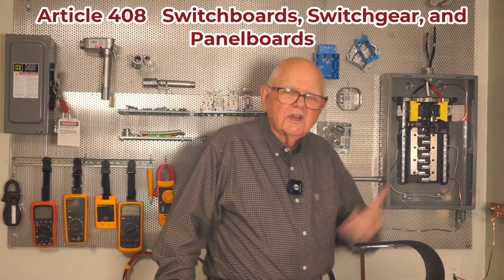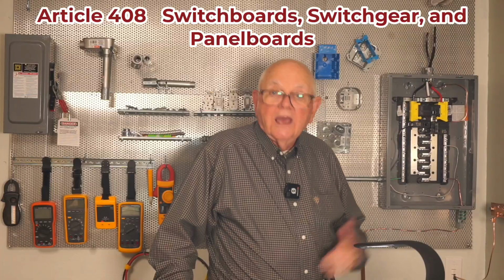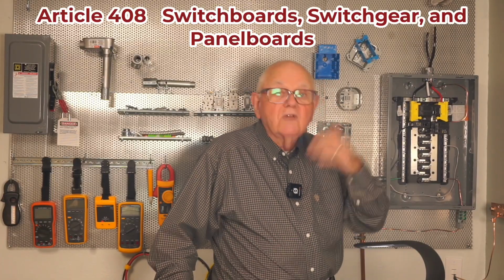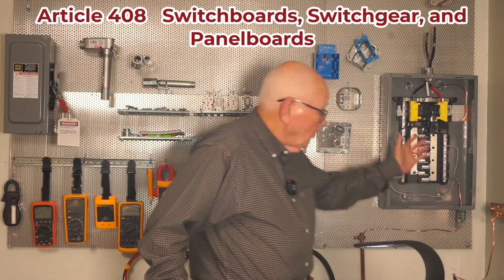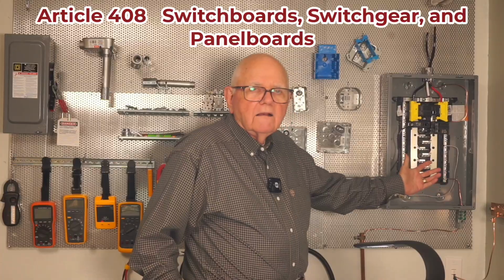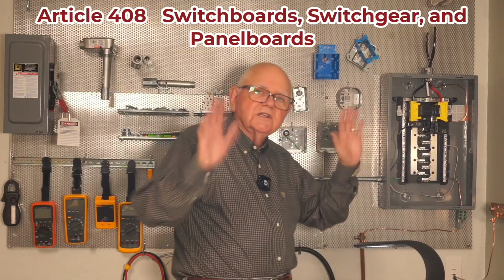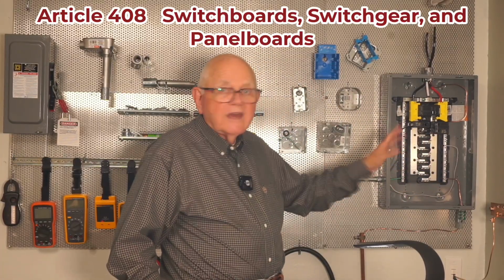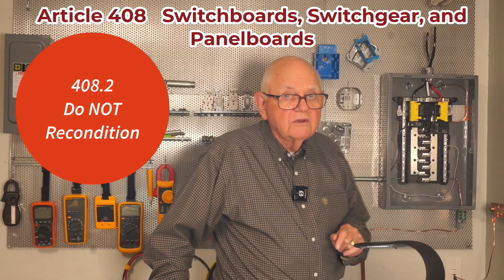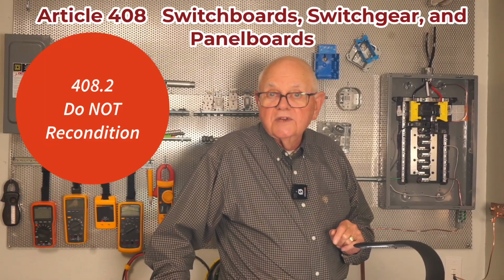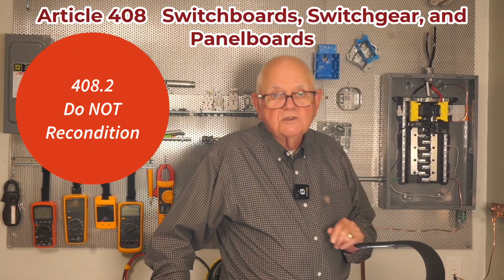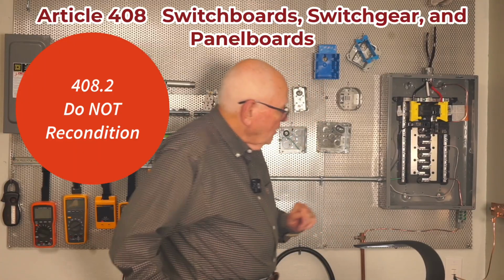So that's not really an installation problem for us, unless we are allowed to, by the way, replace panel boards. We could pull the guts out and replace it with either listed or other than listed. It's all covered in the code. We can do that. We cannot recondition panel boards. 408.2 talks about reconditioning requirements. Panel boards cannot be reconditioned. So anyway, it's bonded to the metal enclosure.